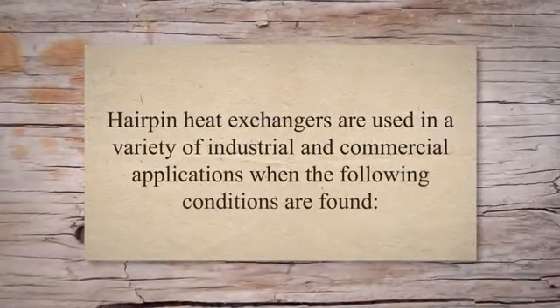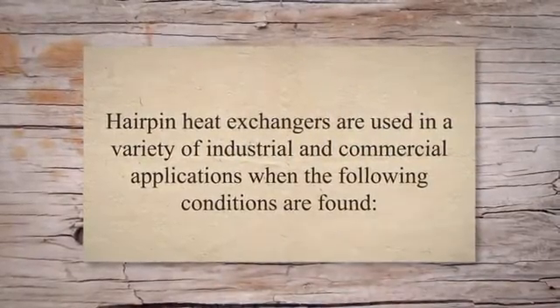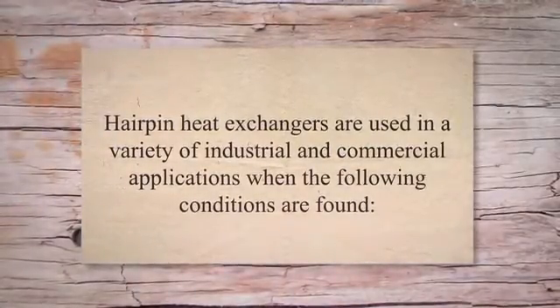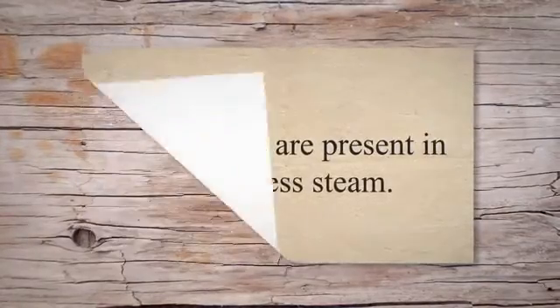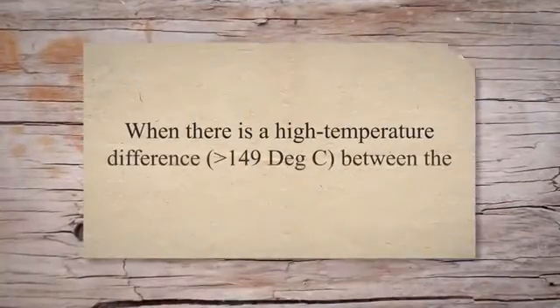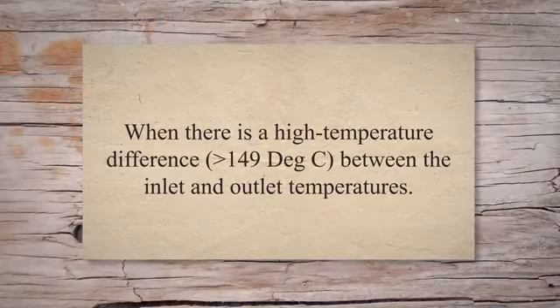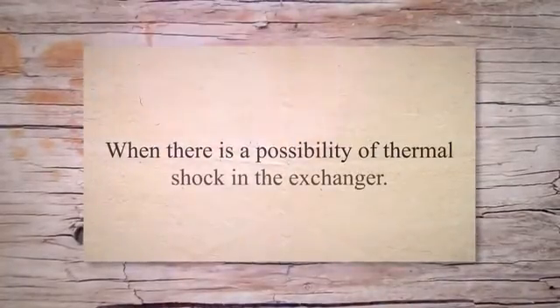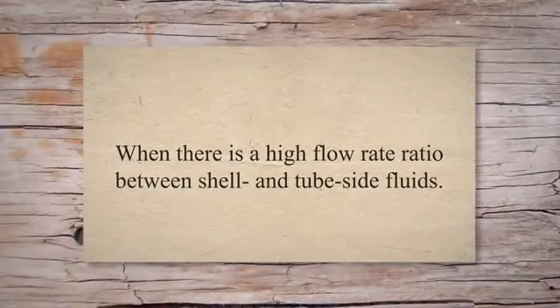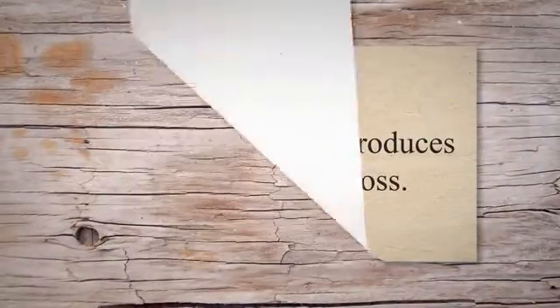Hairpin heat exchangers are used in a variety of industrial and commercial applications when the following conditions are found: when solids are present in the process stream; when there is a high temperature difference (149°C) between the inlet and outlet temperatures; when there is a possibility of thermal shock; when there is a high flow rate ratio between shell and tube side fluids; for cyclic services; and when the process produces a temperature cross.